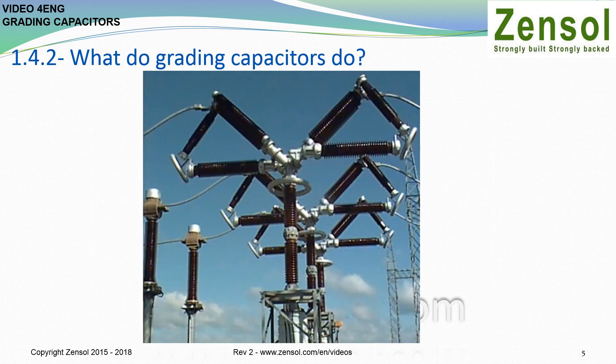What do grading capacitors do? These capacitors are voltage dividers. They are mounted in parallel with each contact to spread the voltage over the main contacts of the circuit breaker. This prevents any contact from being exposed to excess voltage.